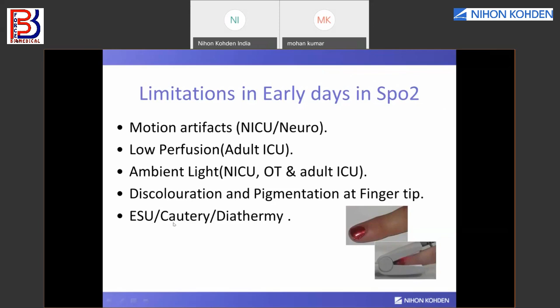Once you place your finger on the SpO2 probe, the signals are picked up from the fingernail, and the analog signals are converted into digital, and these digital signals are passed through various filters. Basically, there are wide band pass filters and narrow band pass filters. After filtration, the raw waveform is displayed on the monitor, and it goes to the next stage where the pulse rate, the SpO2 value, and the perfusion index values are displayed. So what is the perfusion index? The perfusion index is a ratio of pulsatile blood flow to non-pulsatile blood flow in the peripherals. If the perfusion index value is very low, you don't get an SpO2 signal.